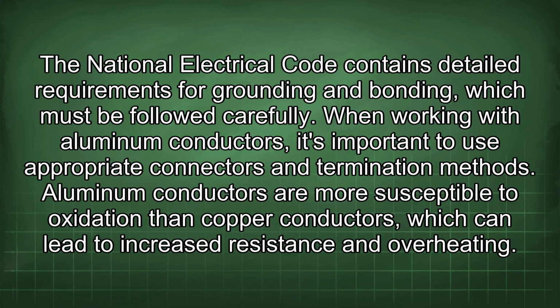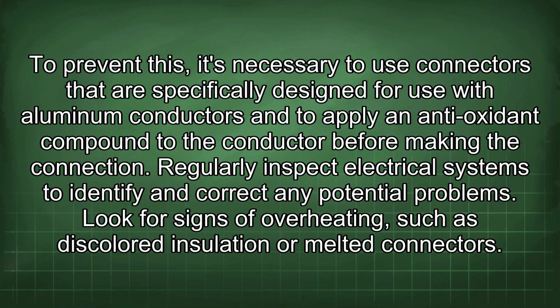When working with aluminum conductors, it's important to use appropriate connectors and termination methods. Aluminum conductors are more susceptible to oxidation than copper conductors, which can lead to increased resistance and overheating. To prevent this, it's necessary to use connectors that are specifically designed for use with aluminum conductors and to apply an antioxidant compound to the conductor before making the connection.